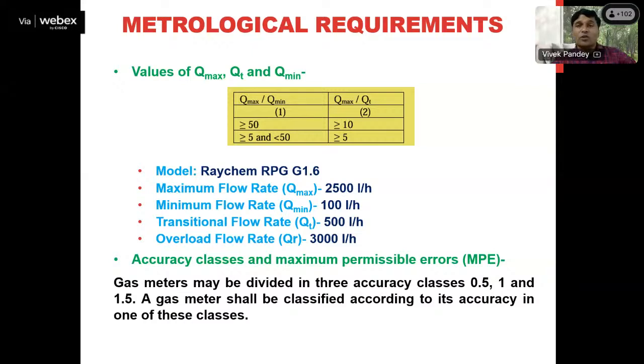Now, in this metrological requirement section, there are 3 accuracy classes specified for gas meters: 0.5, 1 and 1.5. These are the three accuracy classes specified for different gas meters. Whether they are ultrasonic, diaphragm type or positive displacement type doesn't matter. Any technology can be used in all these three accuracy classes. Based upon these accuracy classes, the accuracy levels are specified, meaning the prescribed tolerance. Later on I will show you that also.